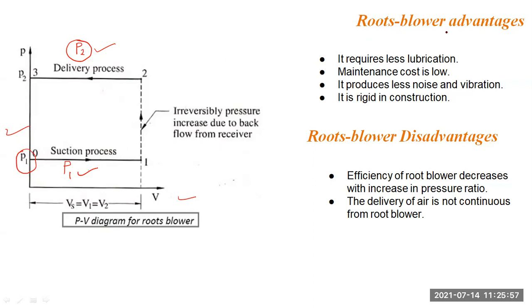Okay. So we have some advantages and disadvantages of root blower. Some advantages are it requires less lubrication. Lubrication would be very less, okay, because it is an open system. So there is less lubrication we require. Maintenance cost is less, okay, because there is no costlier part, there is no cylinder, there is no piston, okay. So that's why maintenance cost of this root blower is less. Noise will be less, vibration will be less, okay, and the construction is very rigid. These are some easy advantages of root blower.